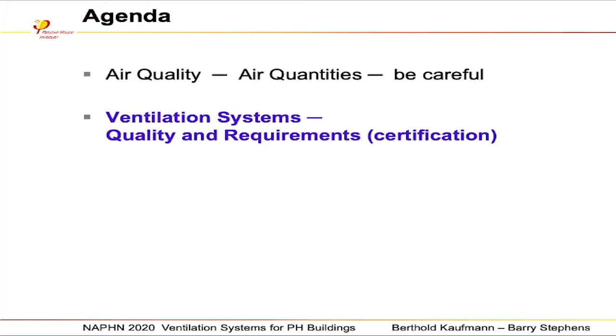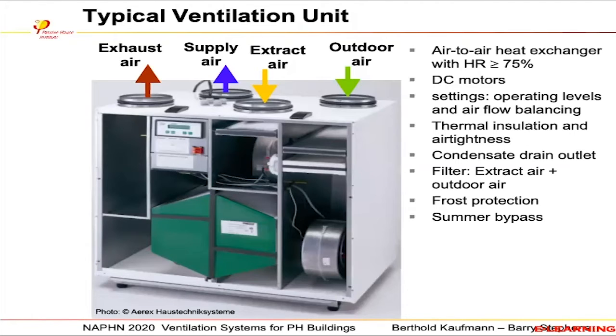proceeding, we come to the requirements for ventilation system in some general point of view. And in the next slide, you see a typical ventilation system, ventilation unit. The green part is the heat exchanger, and you see on the right, the green arrow, outdoor air comes in, and from the fan there, and from the left bottom to the right up, it will be heated up and get to preheated supply air. And the yellow arrow, extract air, is coming from bathroom and toilets and the kitchen, and goes from right top to left below, and will be cooled down and will get out of the system as exhaust air going out.